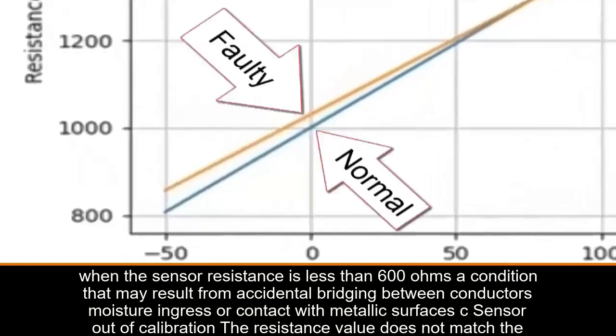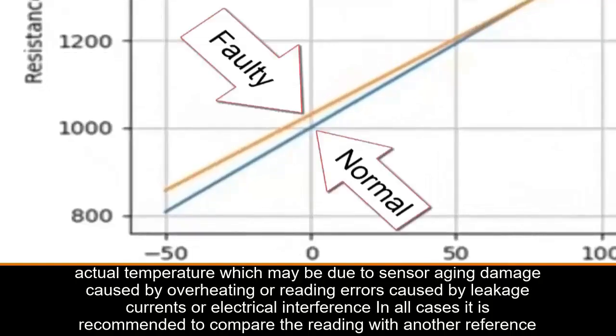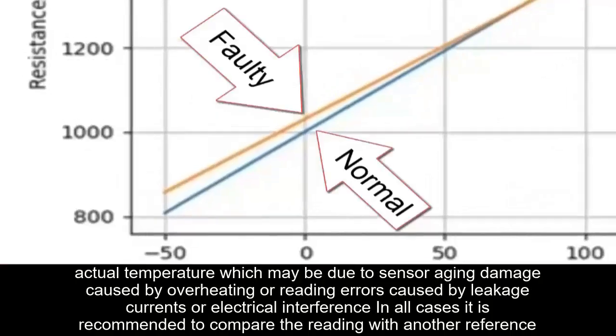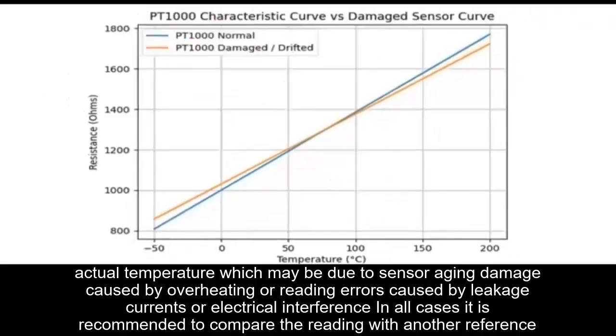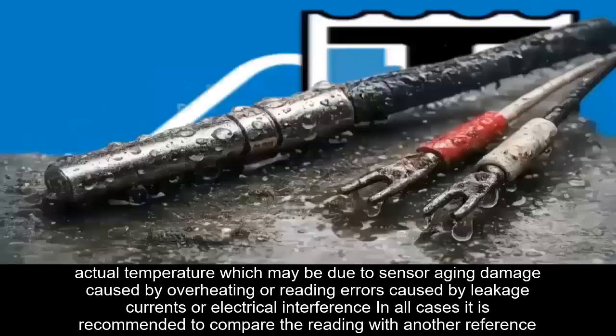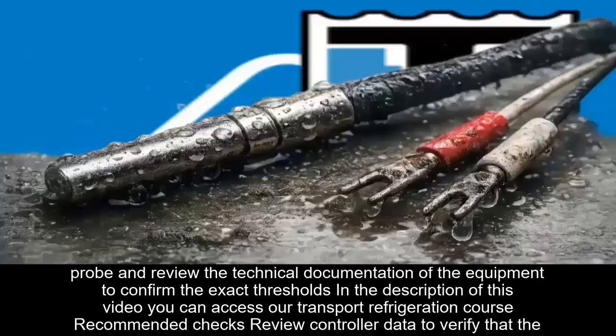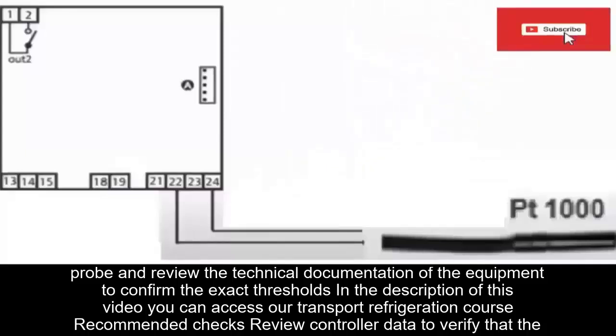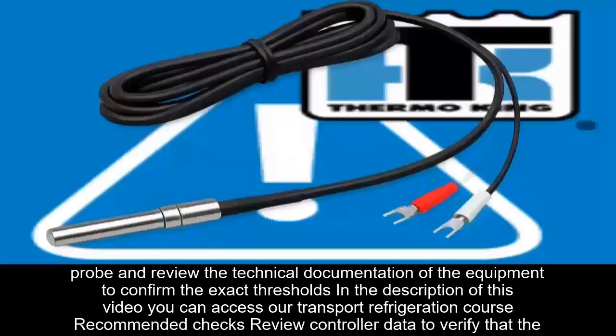Third, sensor out of calibration. The resistance value does not match the actual temperature, which may be due to sensor aging, damage caused by overheating, or reading errors caused by leakage currents or electrical interference. In all cases, it is recommended to compare the reading with another reference probe and review the technical documentation of the equipment to confirm the exact thresholds.